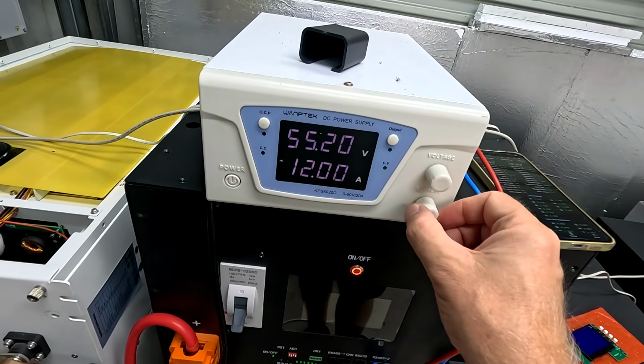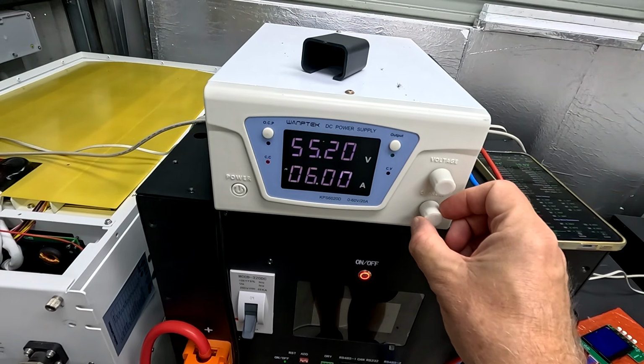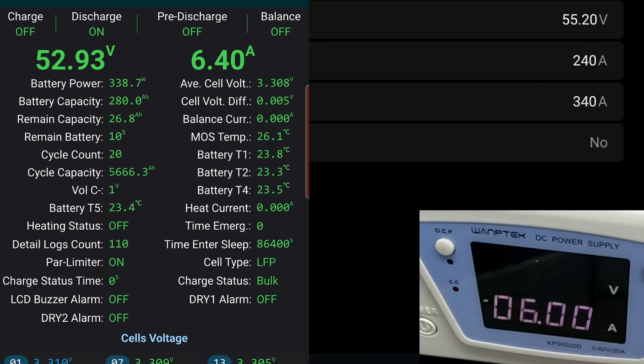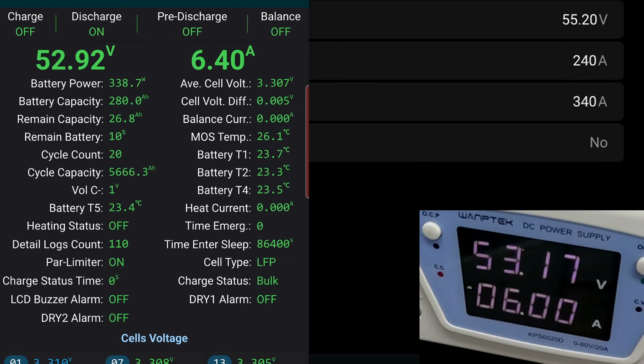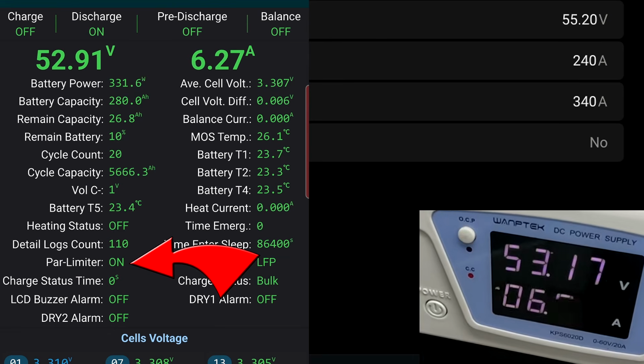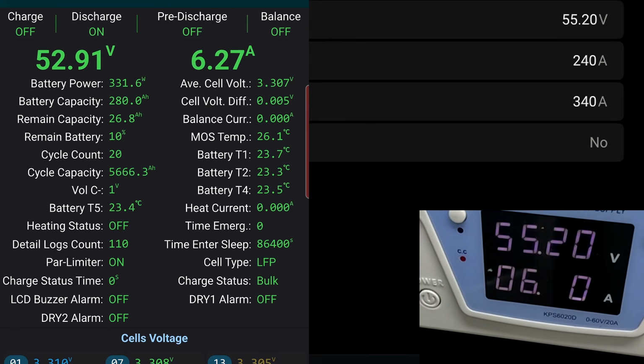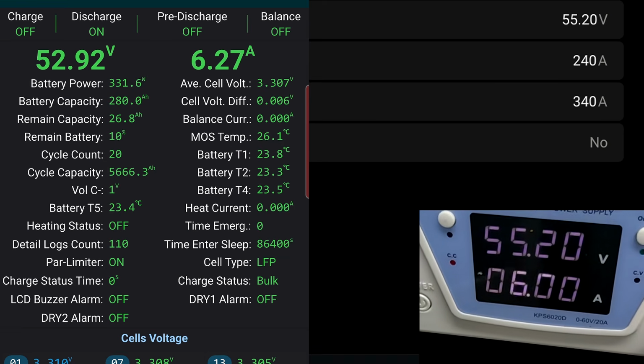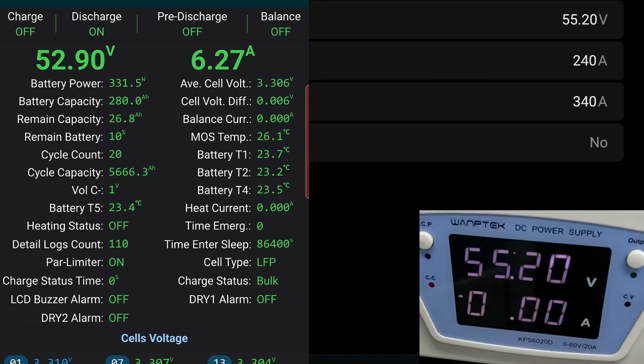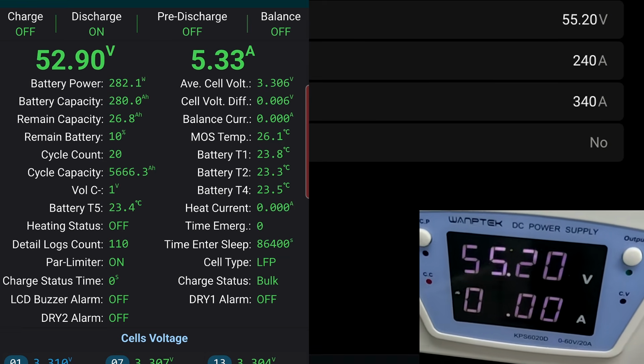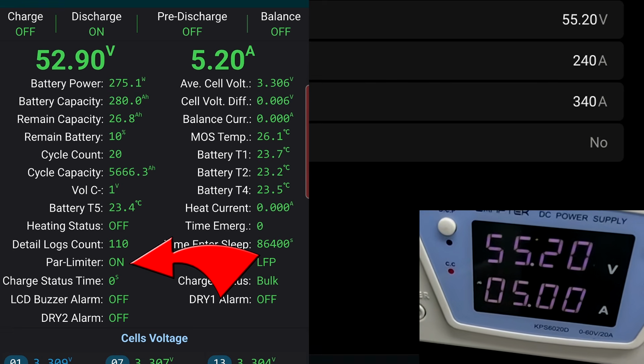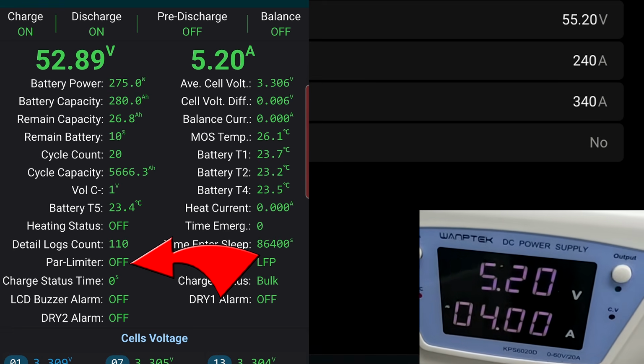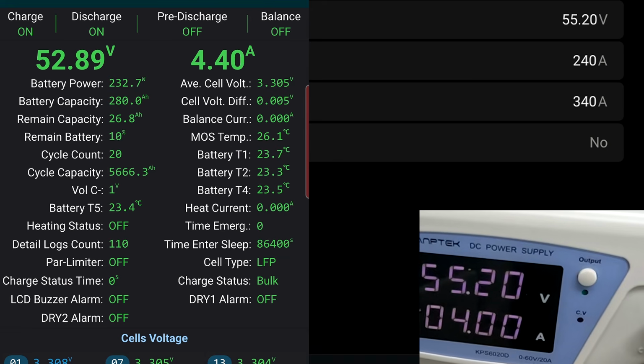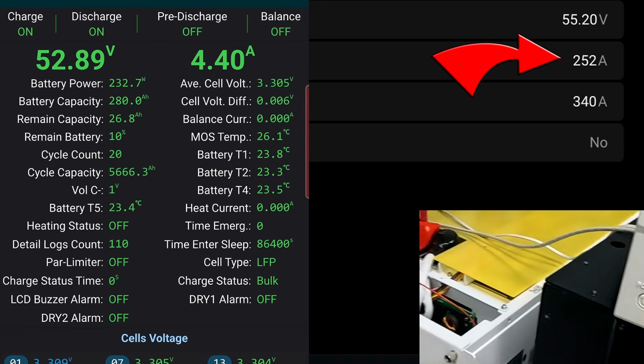Set the current to 6 amps. You can see here on the left the parallel limiter, the charge limiter is on. So 6 amps doesn't do anything. We go one further down to 5 amps. It's 5.2 the BMS shows. And we go one further down to 4 amps. And now the parallel limiter turns off, so it is actually 4 amps.